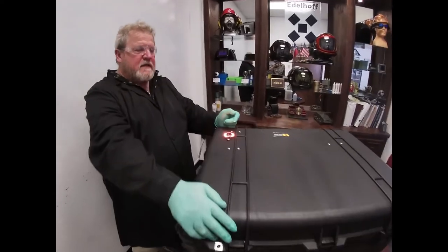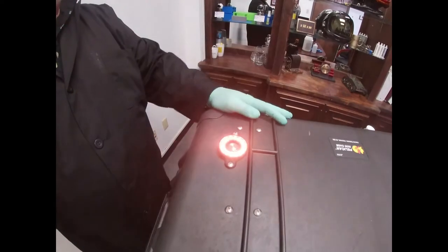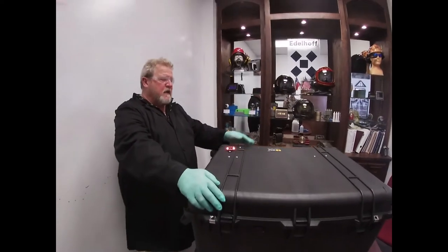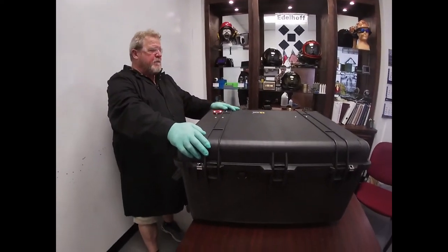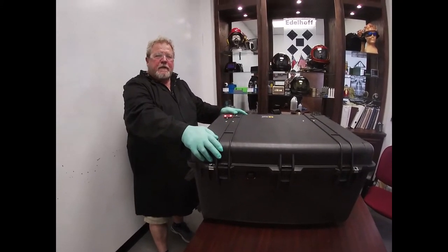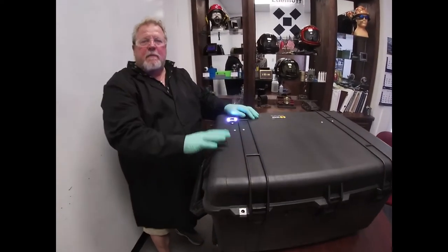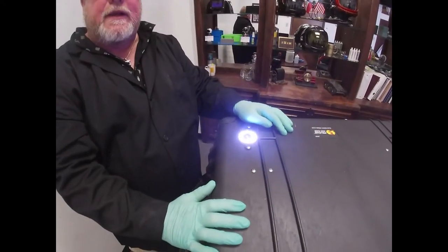As you can see it is now done with the sanitizing. It is now finishing up — all of the vapors that are inside are now being extracted out. The hydrogen peroxide is clearing, and we're waiting for the lights to turn white, meaning that the process is completed. The white light is on — that means that the sanitation is completed on this helmet.